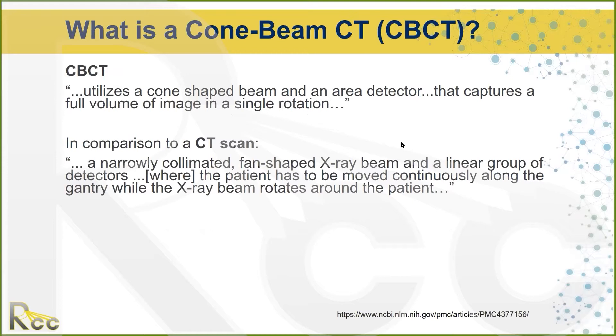So what is a cone beam CT? It's a form of CT — computed tomography. Computed tomography takes projections around an arc around the patient, usually a 360-degree arc, but we'll talk about why 360 degrees isn't always necessary. Instead of taking a two-dimensional image like a radiograph, the CT takes hundreds to thousands of images. Just like an x-ray, the images in a CT are formed by attenuation in the tissue — the x-rays travel through the patient at different degrees depending on the density the beam passes through.